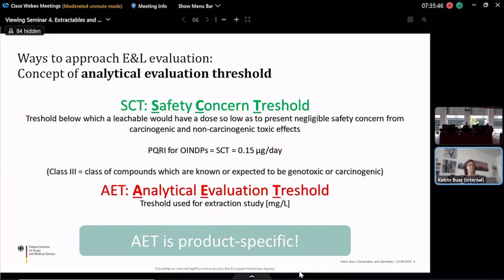And this safety concern threshold can be used to calculate the analytical evaluation threshold based on the allowed daily dose. So you know how your product will be dosed, how large the volume will be that is applied, or whatever kind of dose. And this knowledge can be used to translate SCT to AET. That means that the AET is a product-specific calculation, and it's different for each and every product. Next slide, please.